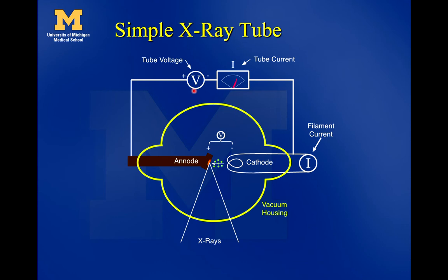You can tune the voltage to whatever you want. This voltage supply creates a voltage gap between the cathode and the anode, which starts the electrons — boiling hot on the tungsten wire of the cathode — to jump across the voltage gap and collide into the anode. As they go from cathode to anode, they're accelerated by the voltage. They hit the anode and either produce heat or make x-rays, and that's how we get an x-ray beam out of it.